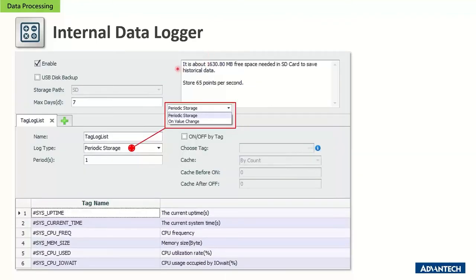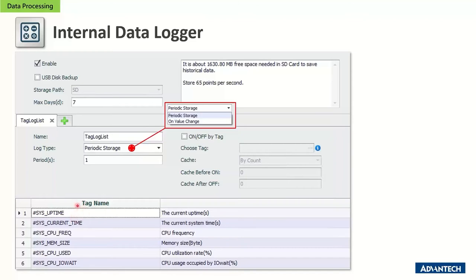To configure the data logger, you enable it and choose the log type: periodic storage or on-value-change. Periodic storage logs data at every set interval — for example, every one second. On-value-change only stores data when a tag value changes, saving memory space on the micro SD. For example, if you add a few tags logging every one second, the utility estimates you'll require approximately 1.6 GB of storage.